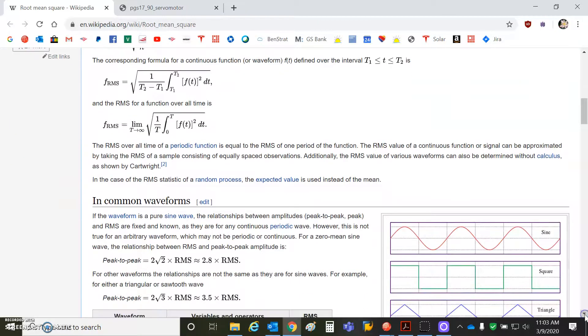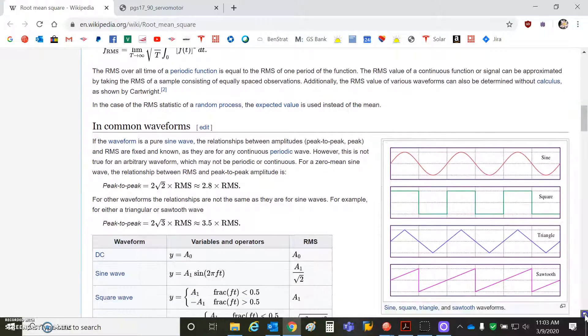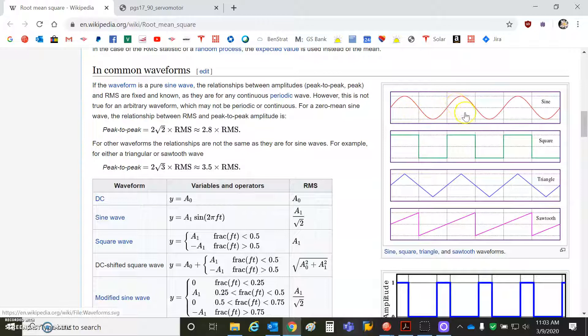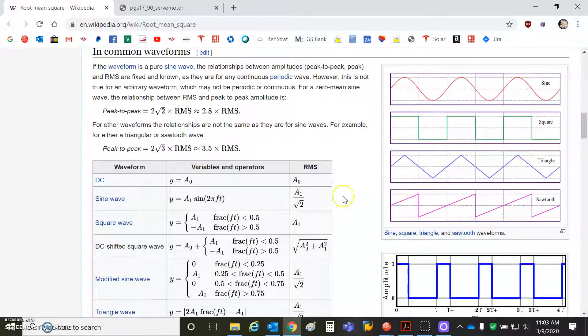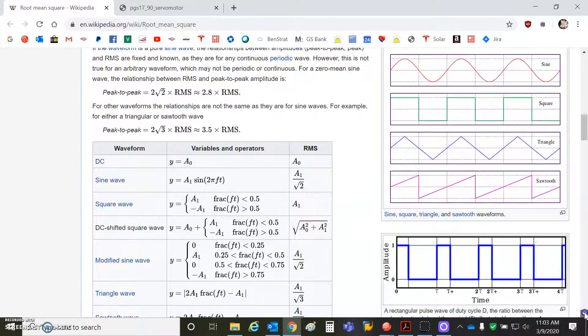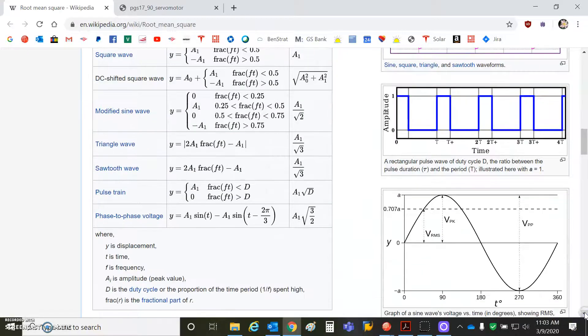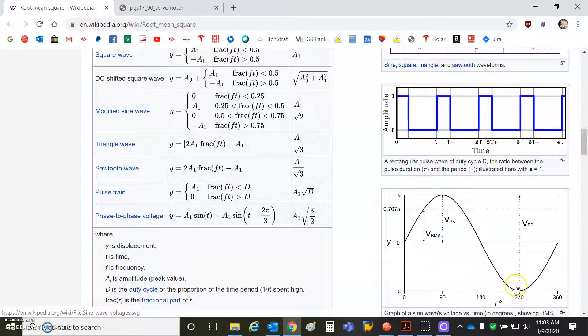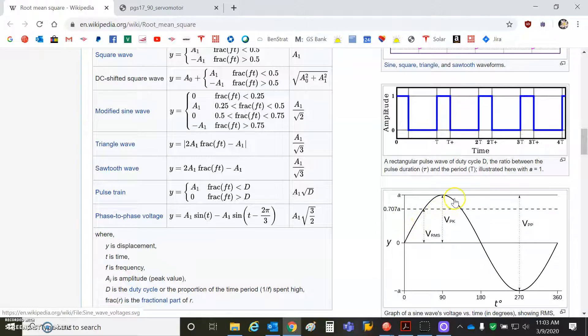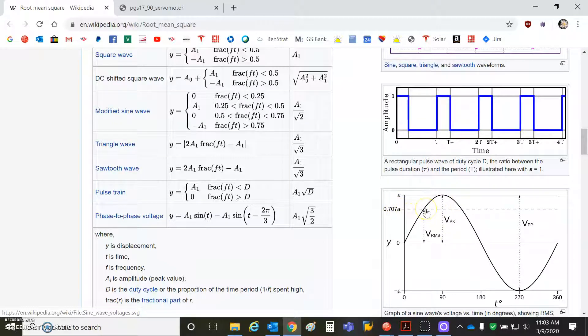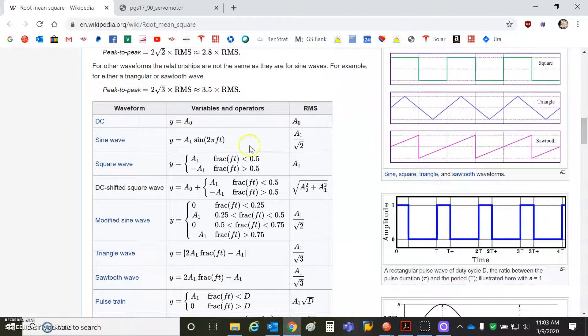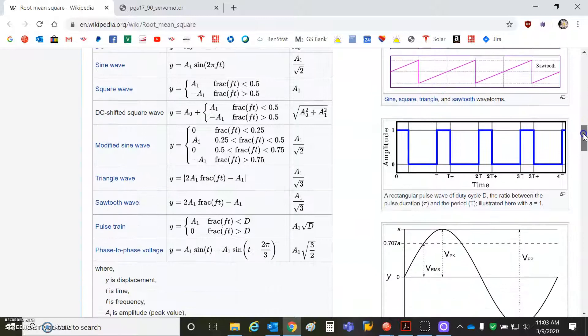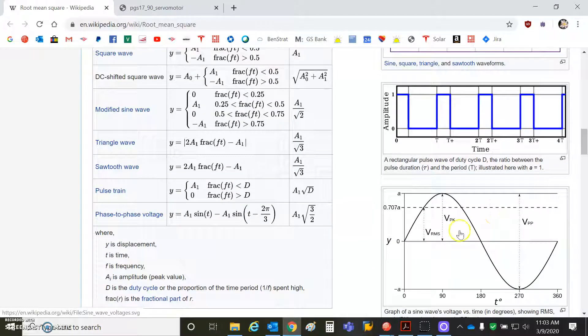So this is a good thing for us to understand. With a brushless motor, you have a sine wave. You'll have a magnitude of the current vector, and then you'll have the RMS of the sine wave, and that's a square root of 2. In other words, if you had a sine wave to your motor, as we're delivering current, whether it's positive current or negative current, we're rotating a current vector to the motor for brushless commutation. So the magnitude of that current vector would be the amps peak, and then the RMS value of that would be 0.707 or 1 over the square root of 2, just like it showed in the table here for a sine wave.